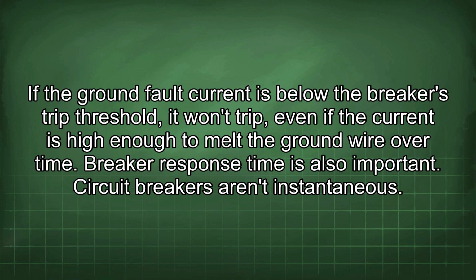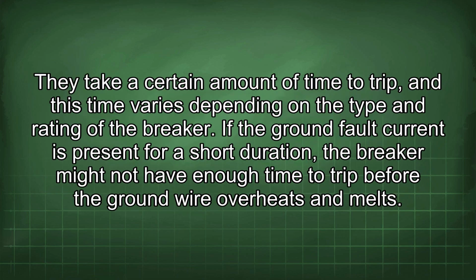Circuit breakers aren't instantaneous. They take a certain amount of time to trip, and this time varies depending on the type and rating of the breaker. If the ground fault current is present for a short duration, the breaker might not have enough time to trip before the ground wire overheats and melts.